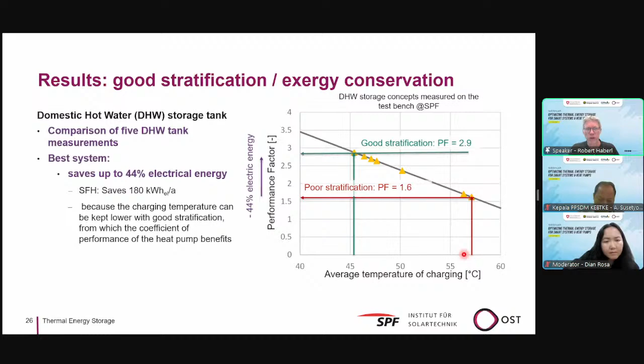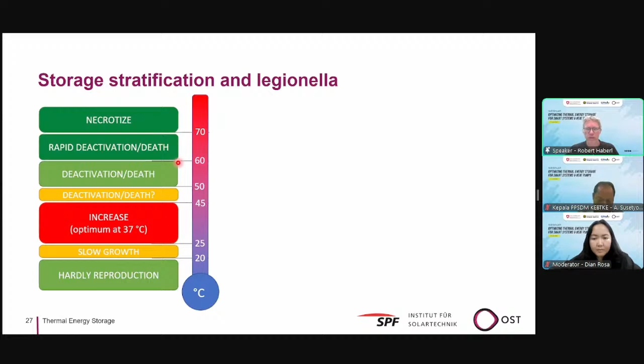Another reason for good stratification is the topic of Legionella. You see the temperature regions where Legionella reproduce. They hardly reproduce at a temperature lower than 20 degrees. There is a slow growth already at 25 degrees, increasing up to 45 degrees Celsius with an optimum at 37 degrees Celsius.